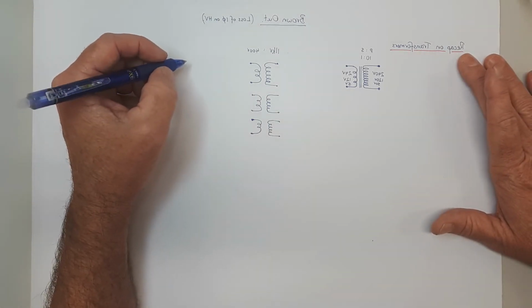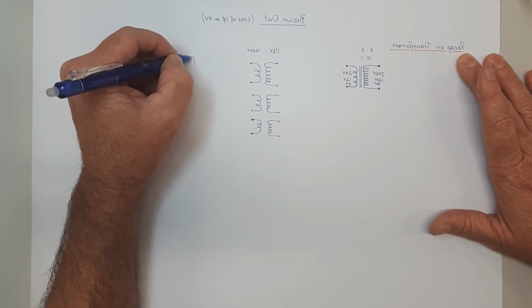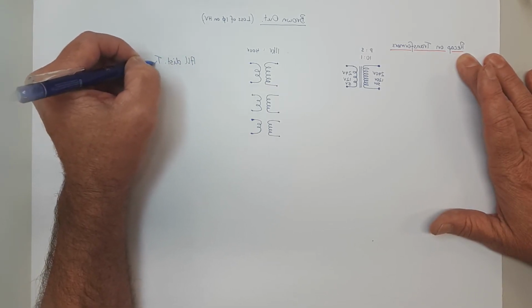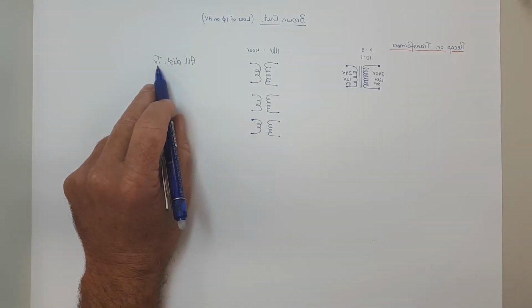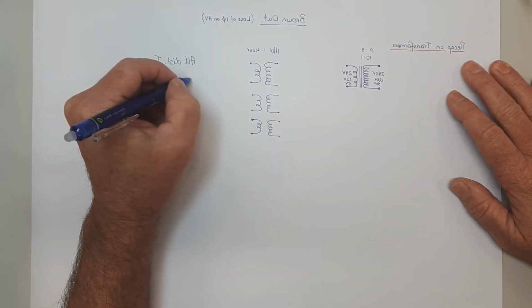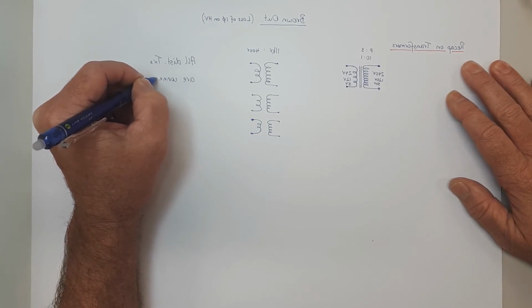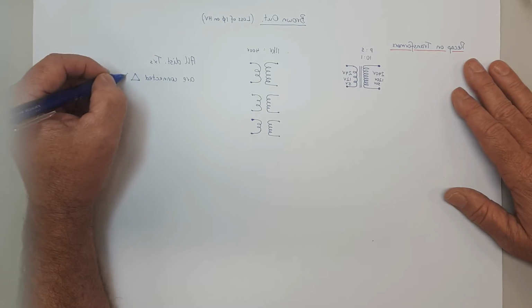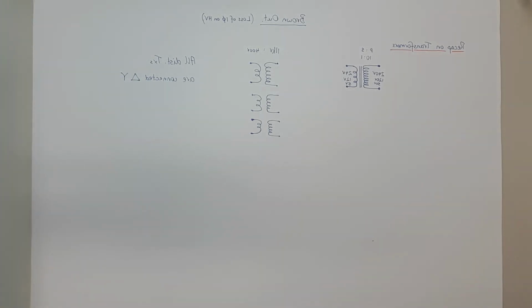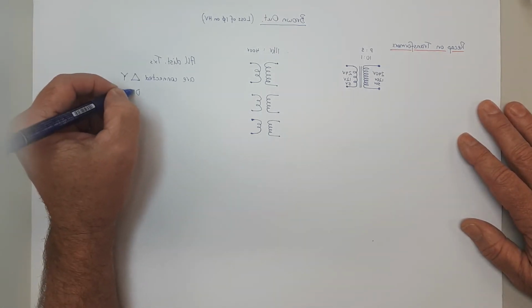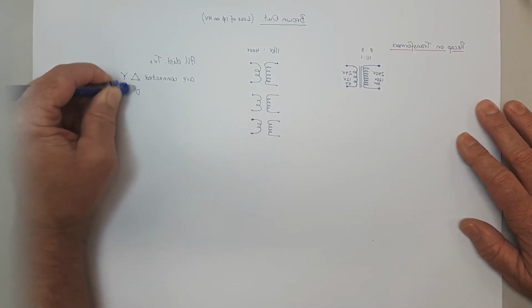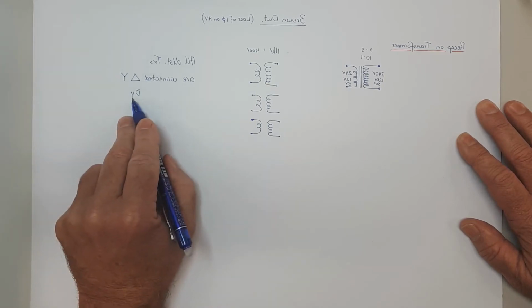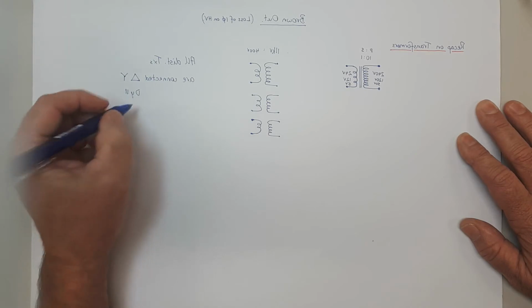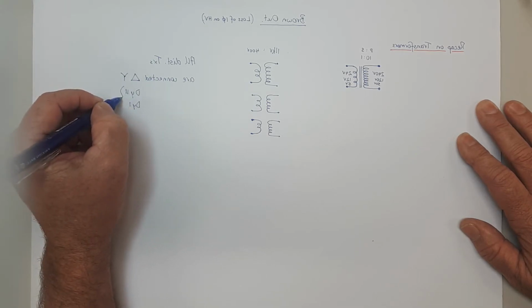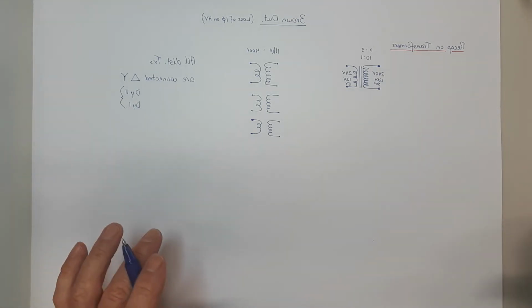Now the key point on all this is that all your distribution transformers, we'll abbreviate transformer, that'll happen a lot, all distribution transformers are connected delta star. Now that's delta, which is symbolized by the Greek letter delta, and Y, that represents star, because that's your star point in there. So we call them DY11. Capital D for the primary, small y for the secondary, and 11. Well, let's not worry about the 11 now because they might be DY1, but the 1 and the 11 aren't important for the purposes of what we're doing here.